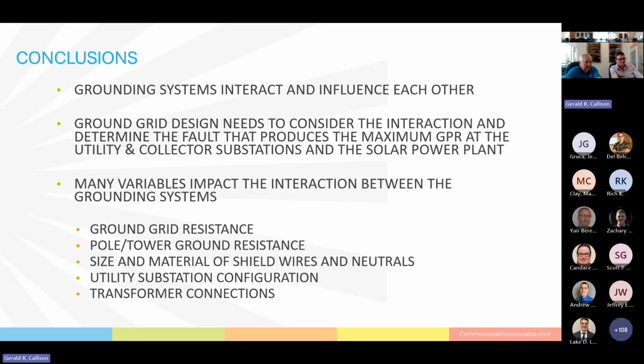As I showed you, the ground grid resistance going from 2.5 to 0.8 ohms made a big difference. If you change the pole grounds, the resistance of those pole grounds will have an impact. The size and material of the shield and the neutrals will have an impact. If you go from a steel shield wire to an aluminum carrier for a fiber optic, the resistance of that is typically much, much lower, and that'll also have an impact on the split factor and the interaction between them.